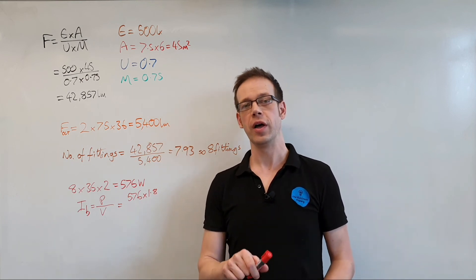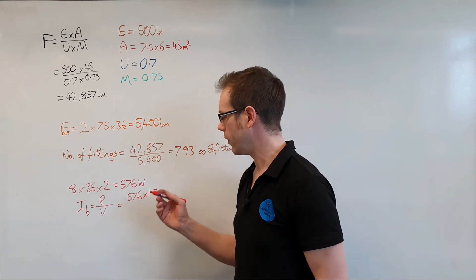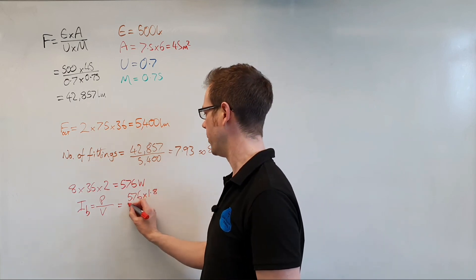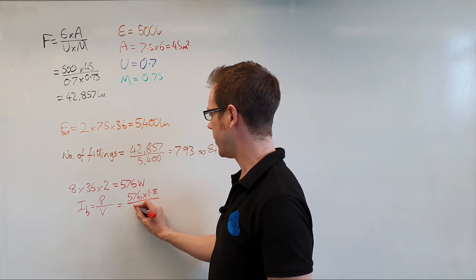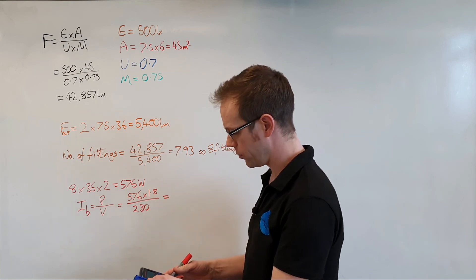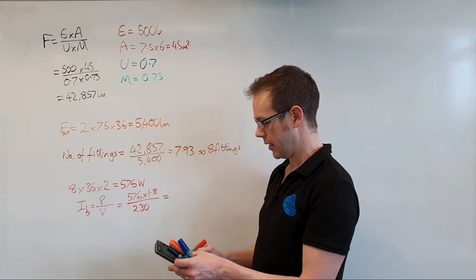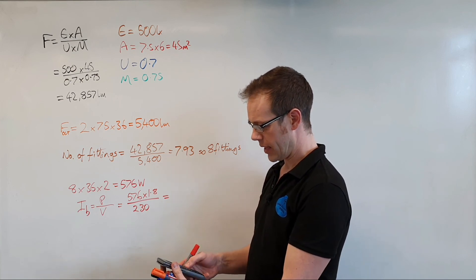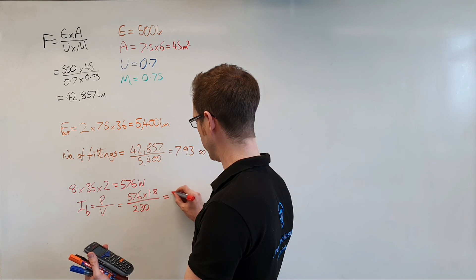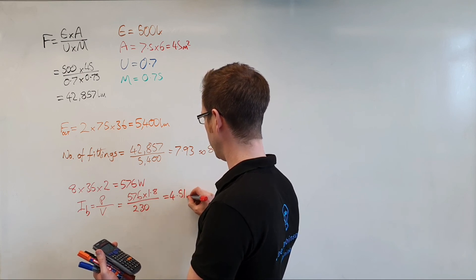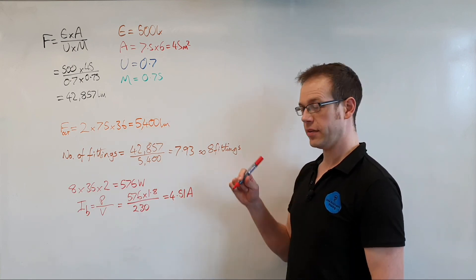Since we don't know the specific power factor of this fitting, we apply the 1.8 multiplier. If you're unsure about this, speak to your electrical lecturer before your exam. So the design current Ib equals 576 times 1.8, divided by 230 volts, which gives us 4.51 amperes.